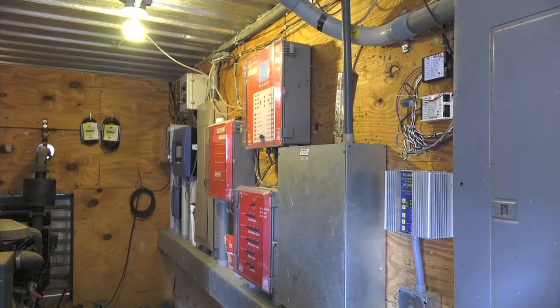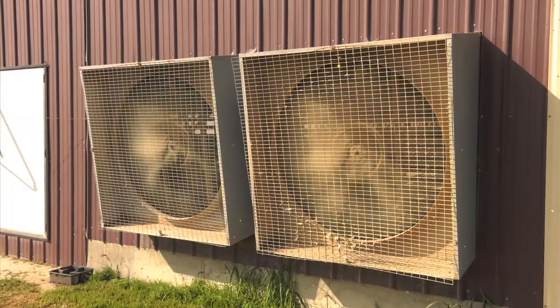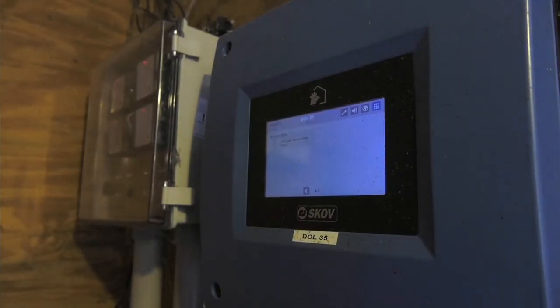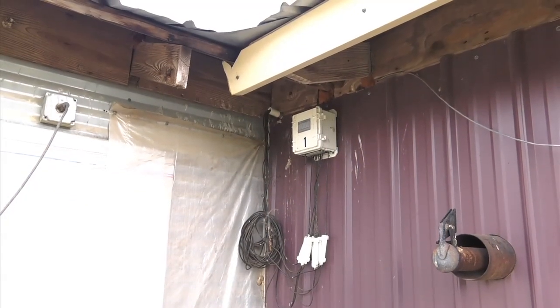The reason for that is these fans are able to change speeds based on the situation instead of constantly running at full speed. If you slow a fan down ten percent, it moves ten percent less air, but it uses thirty percent less power. So all we're doing is slowing down a fan to maybe half or a third of what it normally does. It's still moving the air, we're still providing a great environment for the birds, but we're dramatically reducing our power usage.